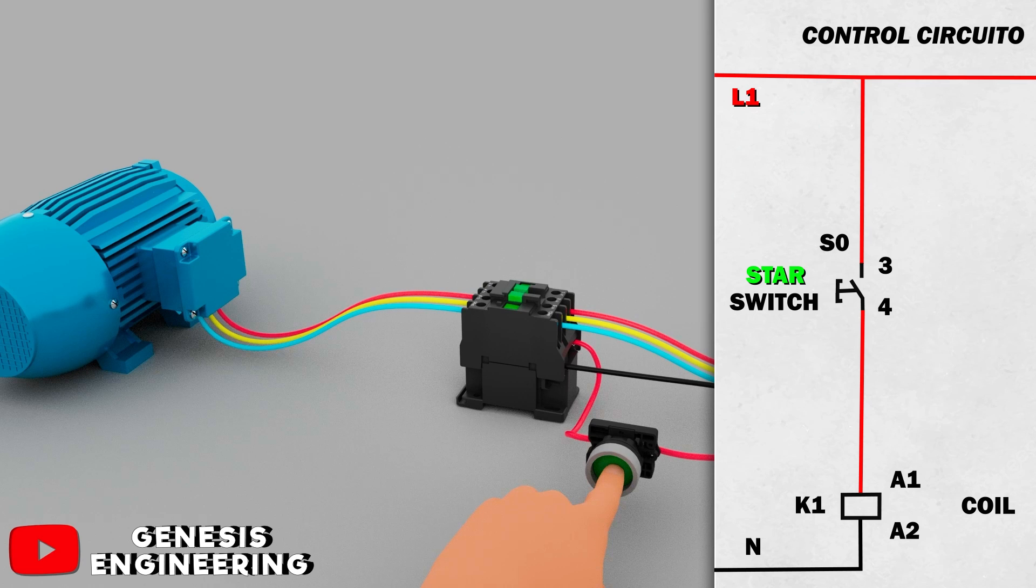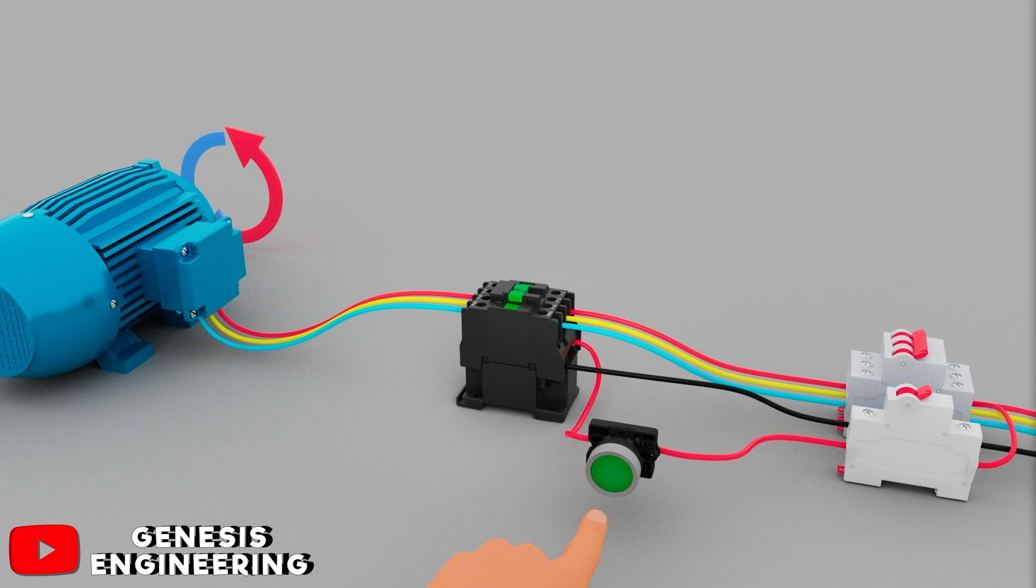When the button is pressed, the contactor will close the contacts and start the motor. However, it is necessary to keep the button pressed to keep the motor running. When the finger is removed from the button, the button returns to the old position and will turn off the motor, which is why we need the contact holding.